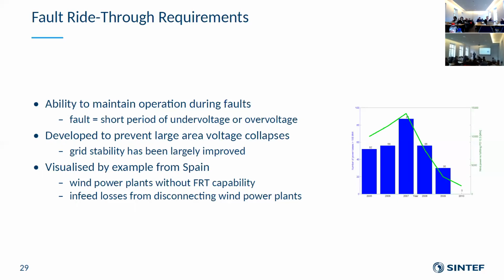As he said, it was the turbine protection that kicked in and shut off. That's always something that will happen, because there's no way any grid code could overrule this internal protection of the power electronics. They're really sensitive and cannot handle overload for any relevant time, they overheat in a millisecond.